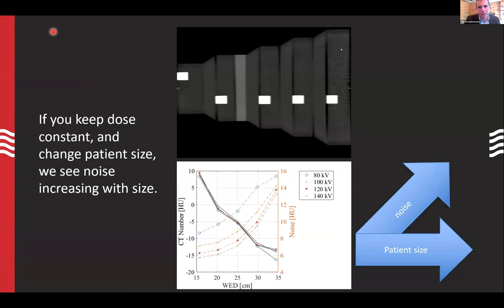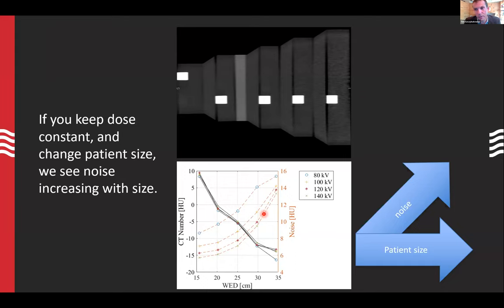If we keep the dose fixed and look at noise varying across different patient sizes — shown here in the Mercury Phantom, which changes size and resembles the Mercury spaceship — we can see that noise is going up as the water equivalent diameter increases. We can see this clinically: if you've got a cardiac protocol that uses the same MA every time, all the big patients' images are really noisy. The noise more than doubles just because of patient size, going from around 6 HU per unit up to around 15 HU per unit.